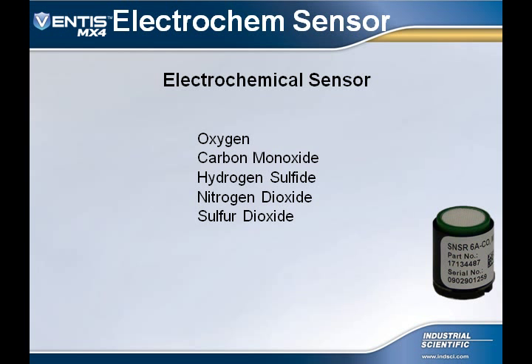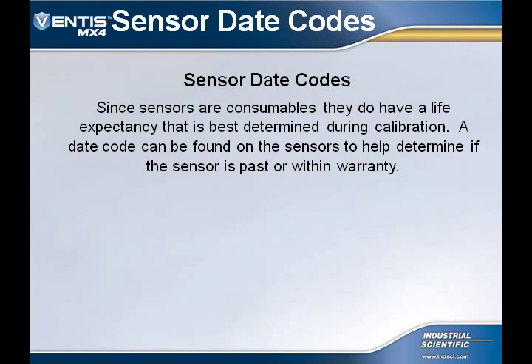Electrochemical sensors that are available for the Ventis MX4 are oxygen, carbon monoxide, hydrogen sulfide, nitrogen dioxide, and sulfur dioxide. The Ventis MX4 has a 2-year warranty, but as mentioned before, the sensors in the instrument have a life expectancy that can be best determined during calibration. A date code is also provided on the sensors to help determine if it's past or within warranty.